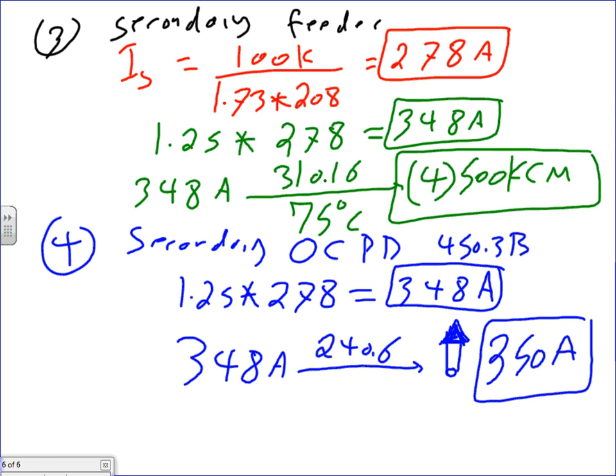Where did the 278 come from? 278 is the full load of the transformer. Oh, the full load of a transformer. Good point. It's the full load of the transformer on the secondary side. Okay, so we have our fuse sized.